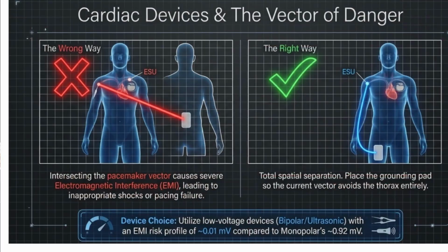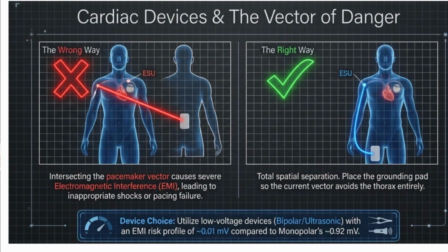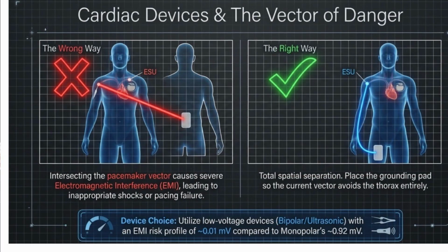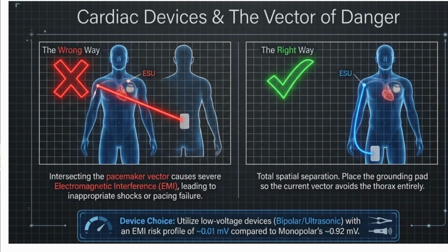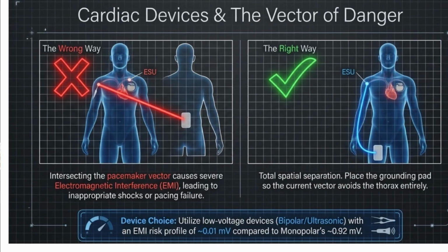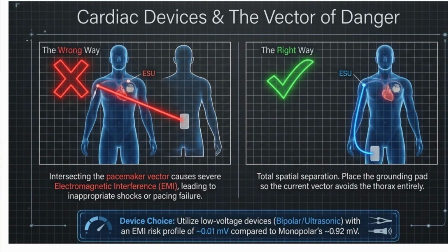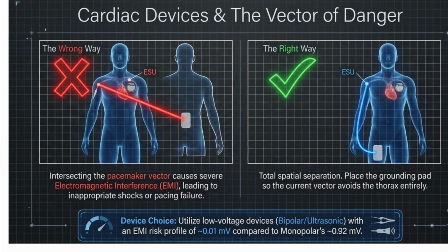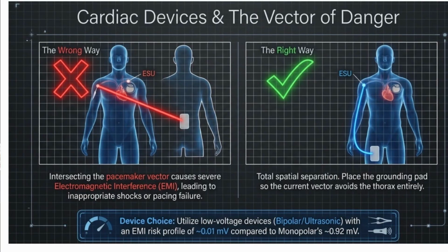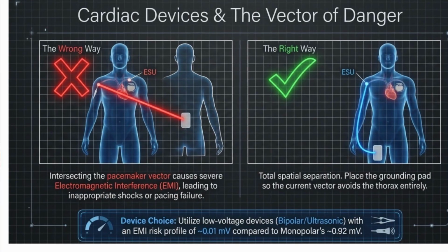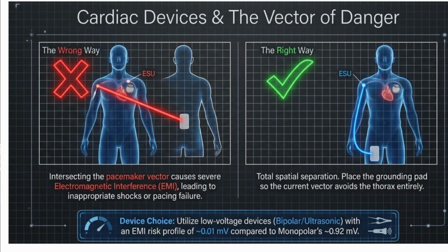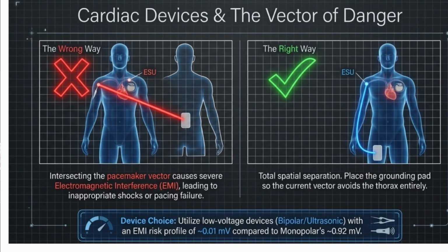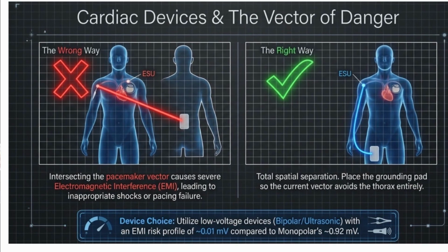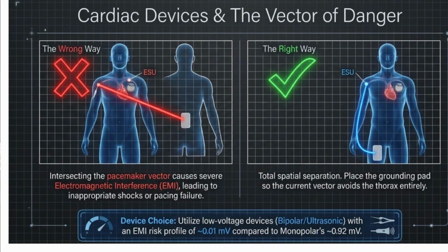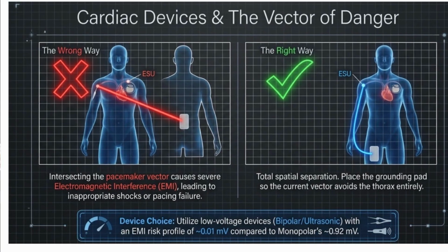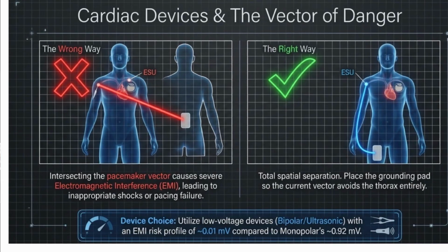Cardiac devices and the vector of danger. Intersecting the pacemaker vector causes severe electromagnetic interference, leading to inappropriate shocks or pacing failure. Ensure total spatial separation and place a grounding pad so the current vector avoids the thorax entirely. The device of choice: utilize low energy devices, bipolar or ultrasonic, with an electromagnetic interference profile of approximately 0.01 millivolts, compared to monopolars with approximately 0.92 millivolts.